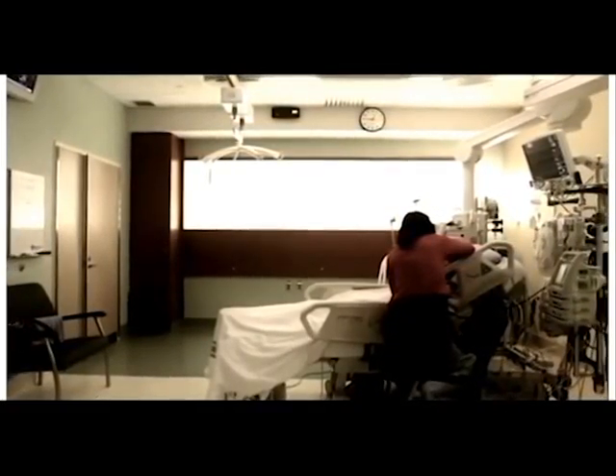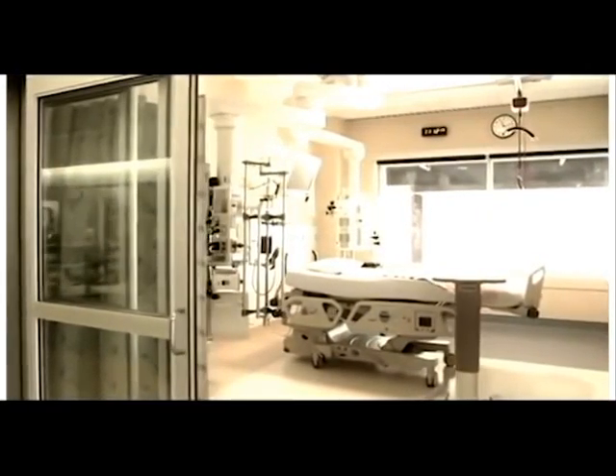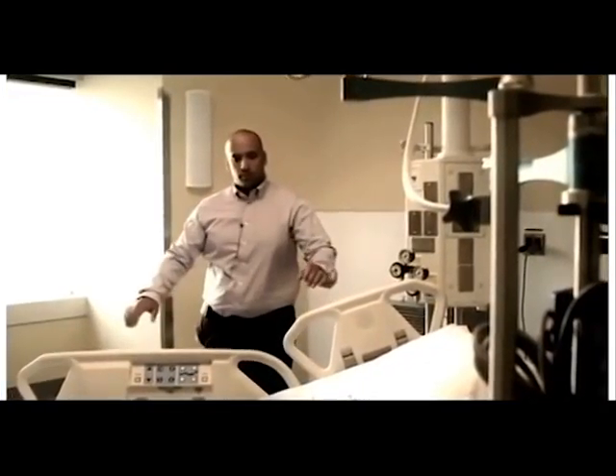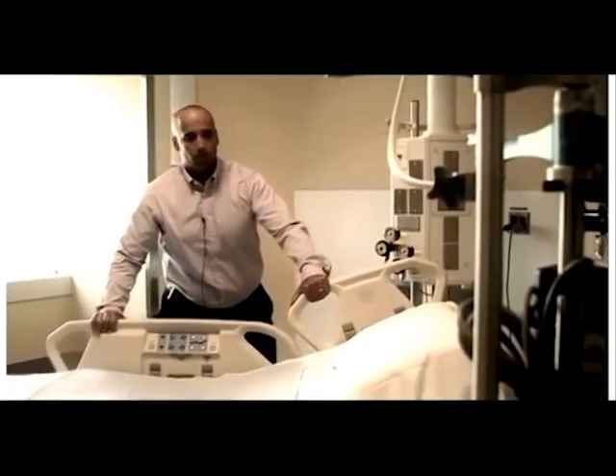With a dual power column concept, the footprint will remain small. The real innovation in these products is the ability to swing the orbiting arm to a variety of locations and degrees that allows for a portable C-arm fluoroscope to operate at the bedside.